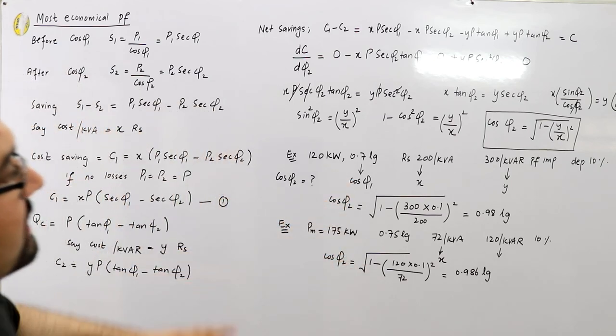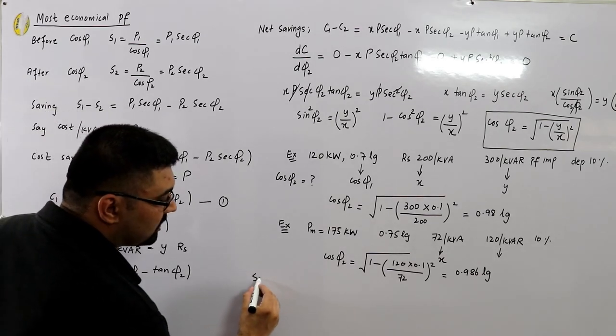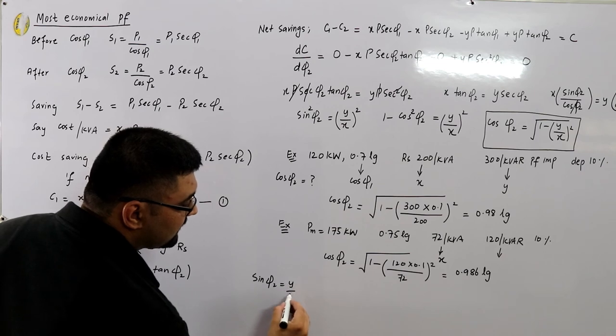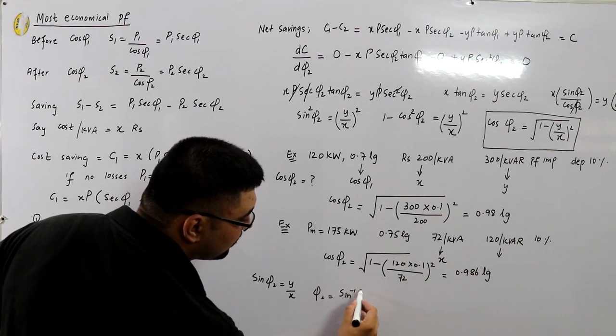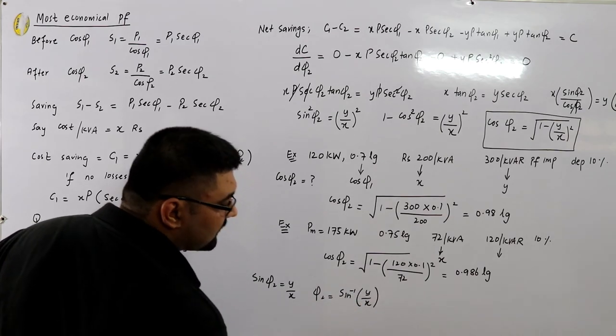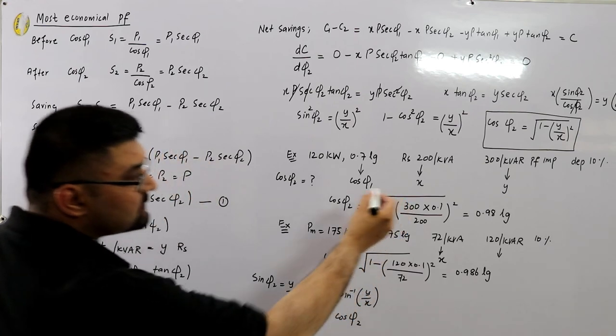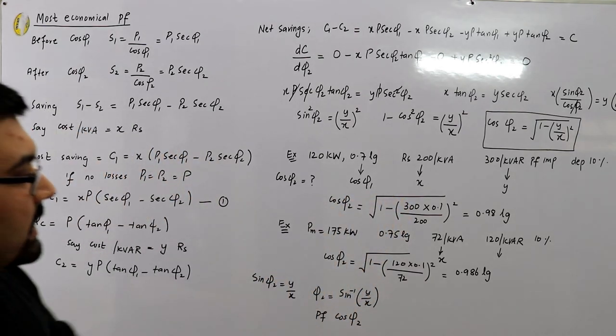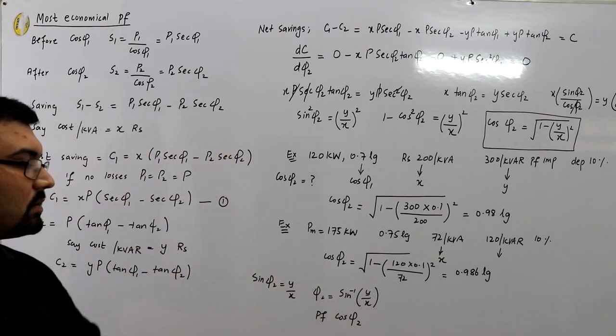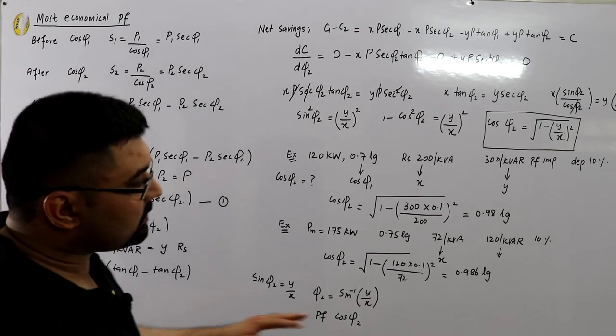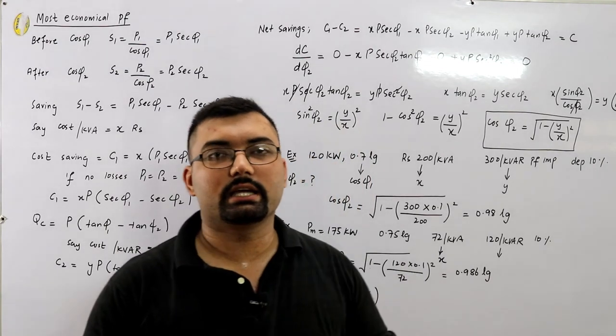To summarize: when you reach the step sin(φ2) = Y/X, you can find φ2 = sin⁻¹(Y/X) and then take cos(φ2) for the most economical power factor. Y is the cost per kVAr of improvement equipment and X is the cost per kVA of maximum demand. I will finish this video here and cover one or two more examples in the next video. Take care, goodbye.